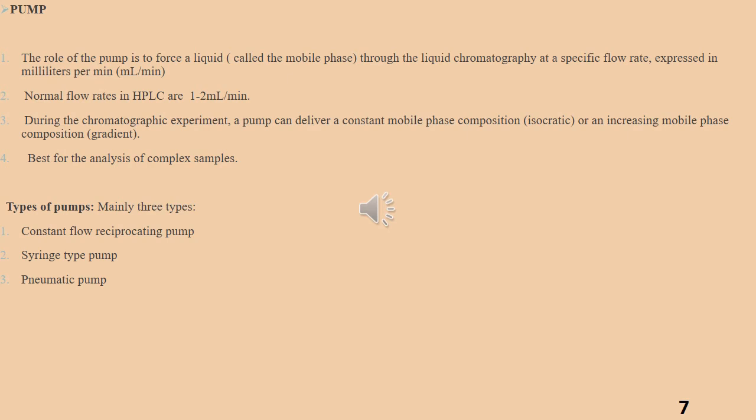They flush solvents simply by a push button action of a purge valve. Dual syringe pumps have also been developed in which one piston is delivering the solvent to the column while the other one is refilled from the reservoir. The material in contact with the liquid allows the use of most solvents including chlorinated hydrocarbons, detergents and oxidizing agents. Now, what are their advantages? It potentially has quite stable flow delivery because no check valve has to be activated during analysis.